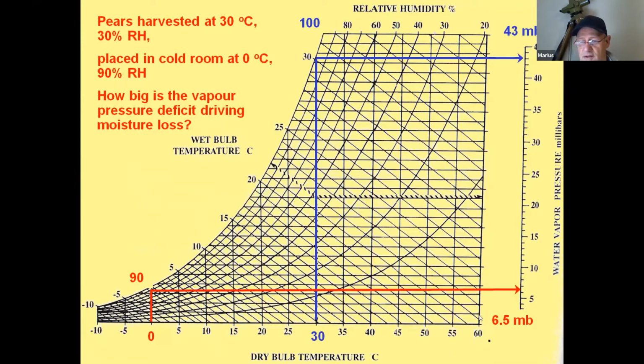So in other words, if you're looking at the specific humidity axis, which is over there, you can see that the amount of moisture in the air is actually very, very little. So the degree of saturation is high, but the absolute amount of moisture is very low. So cold room air is dry air. That's a fundamental principle. So now looking at the vapor pressure deficit, it's 43 less 6.5 gives us a 36.5 millibar deficit. So the situation for the fruit is actually worse than it was in the orchard. We went from a 29 millibar deficit to a 36 millibar deficit. So it's pumping out even faster.